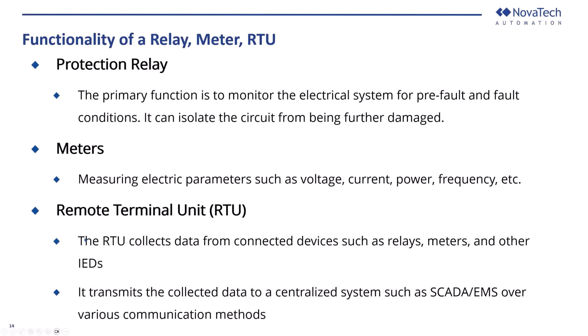Like we said before, fault detection is the primary goal. It identifies faults like short circuits, ground faults, or any imbalances in the phases or ground in the system. It can also isolate the fault by automatically opening or tripping the circuit breaker, so we don't spread the fault further and isolate it from the rest of the system. Another function of the protective relay is to prevent cascading failures and limit the spread of damage to other parts of the electrical network.